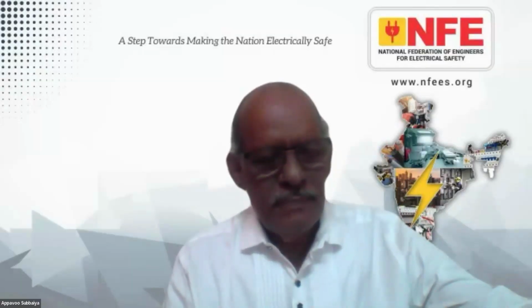Well, as such, electrical safety audit report - this term is not recognized anywhere in the regulations. There are inspection reports given under Schedule 2 of CEA regulations - Form 1, Form 2, and Form 3. But electrical safety audit, what Madam is expecting, may be done as per IS 732 clause 6, where in detail it has been given how the electrical installation shall be tested. Still, it is not clearly recognized under the CEA regulations. Of course, in a way we can say that at some places it has been mentioned that the installation shall be tested as per the standards. So IS 732 is one of the standards, and as per that standard you can use those forms given in IS 732 for safety audit.